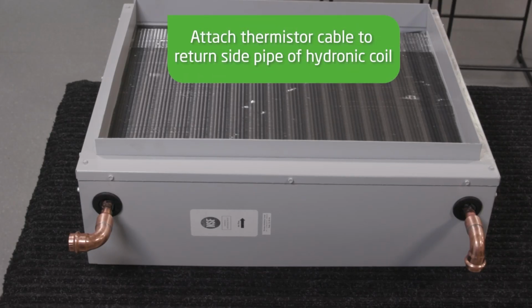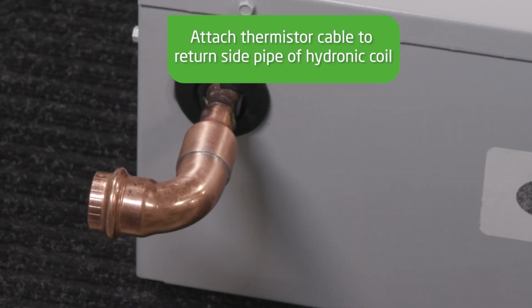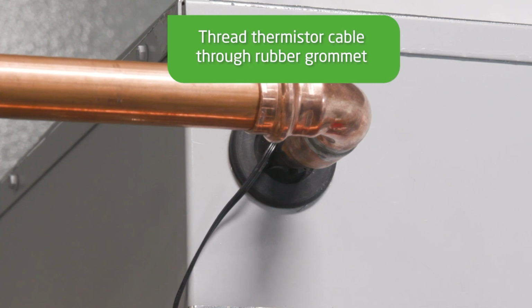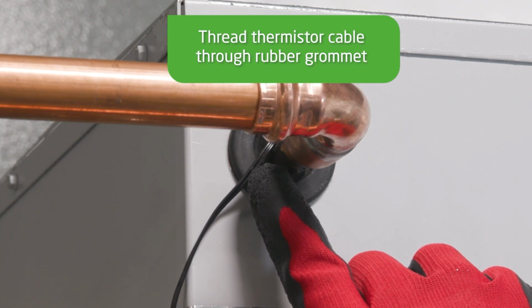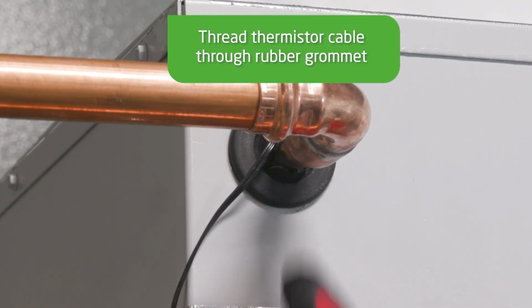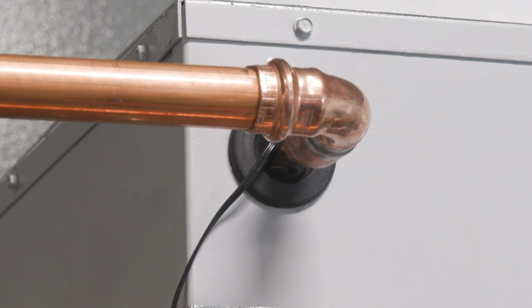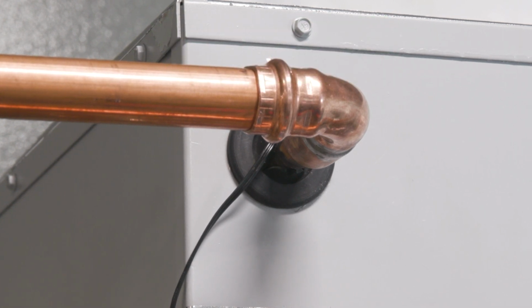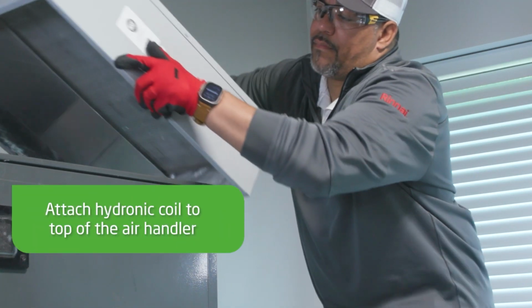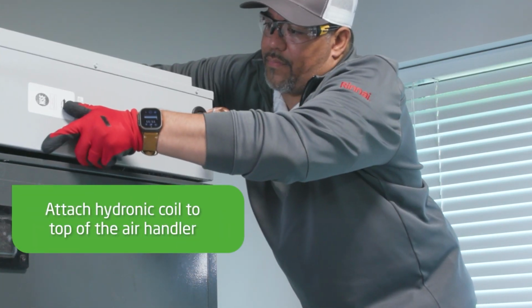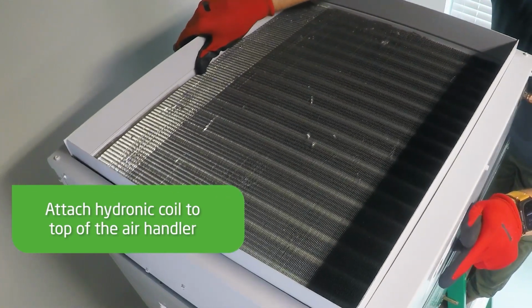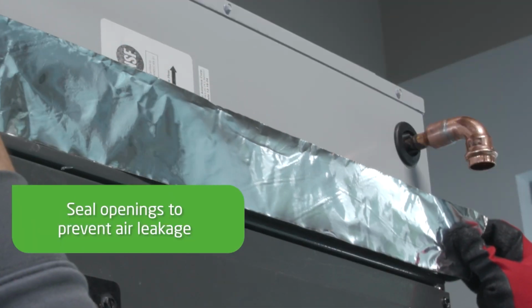Attach the thermistor cable using the clamp to the return side pipe on the inside of the hydronic coil. Now thread the thermistor cable through the rubber grommet in the hydronic coil casing so the wire hangs outside, while the sensor remains clamped on the inside of the return side pipe. Attach the hydronic coil to the top of the air handler and seal any openings to prevent air leakage.